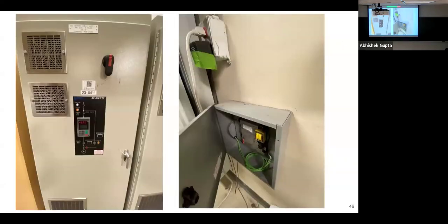We have a VFD, a variable frequency drive, on the left — you can see it's 480 volts, and the key to open it is tied to it. Over here we have a PLC used for routing lighting control system information. Notice the transformer is taped up at the top. Often people in these rooms use outlets for various equipment, like charging a laptop. This should be hardwired — we should not be using outlets to power control systems.